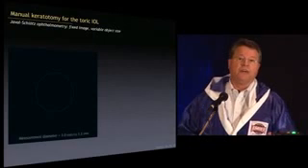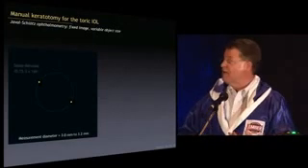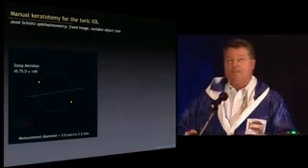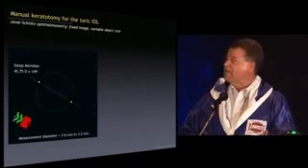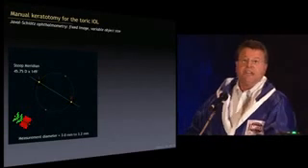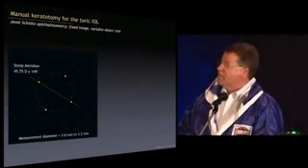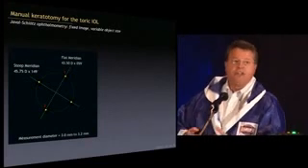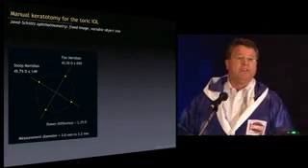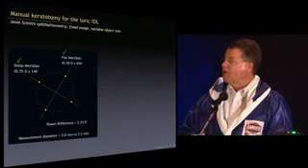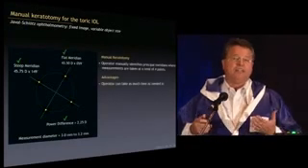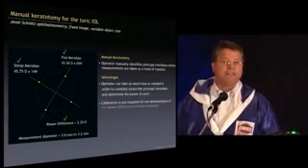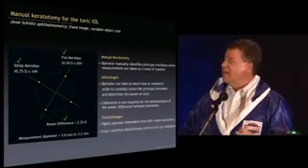So why does a manual keratometer work so well? This is what the manufacturer recommends. If you're off on your axis, you actually get a picture and you get told that you're in the wrong place. When you're in the right place, you get a good picture. Here's the steep axis, or steep meridian, and the flat meridian — what we're looking to do is tell the power difference to give us what we need for the toric IOL. With a manual keratometer you're only measuring four places, but it turns out they're the right four places with the right information.